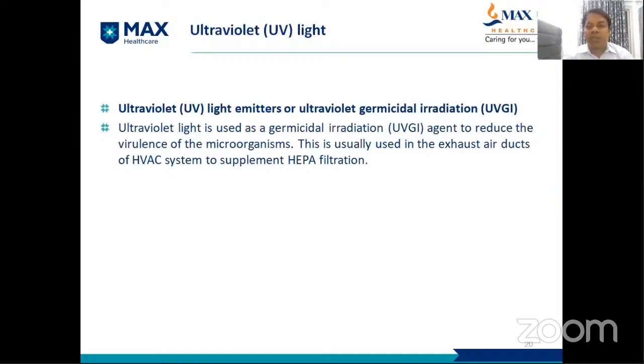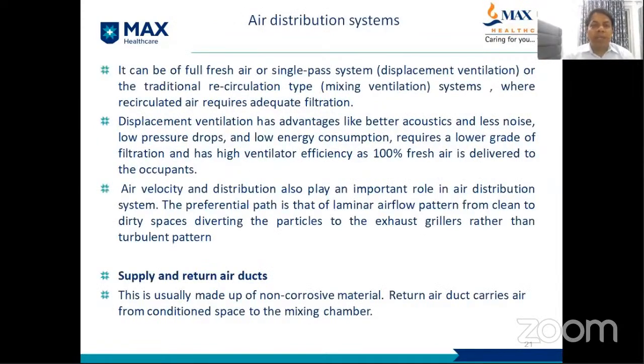Coming to ultraviolet light. Ultraviolet light is used as a germicidal irradiation agent to reduce the virulence of microorganisms. This is usually used in the exhaust air ducts of the HVAC system to supplement HEPA filtration. Coming to the air distribution system, it can be full fresh air or single pass systems like displacement ventilation, or the traditional recirculation type like mixing ventilation systems, where recirculating air requires adequate filtration. Displacement ventilation has advantages like better acoustics and less noise, lower pressure drops and lower energy consumption, and it requires a low grade of filtration and gives high ventilation efficiency, as 100% fresh air is delivered to the occupants.